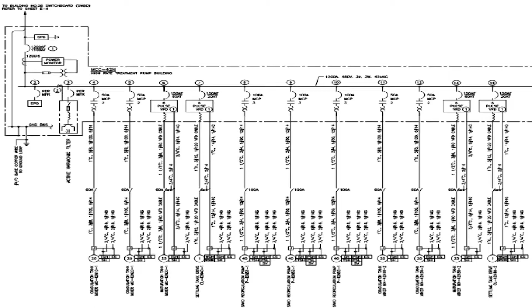Throughout the system we have many transformers to bring down the voltage, other boards, and ultimately we show all these circles on the bottom, which are the individual motors. We show all the power, the circuit breakers feeding that, the starters, and we size all the wires going to it. These drawings show the main breaker size way up here, the individual breaker sizes, and this is actually a motor starter, a different type. This is a VFD, which helps change the speed of the motor, which I talked about a little earlier.